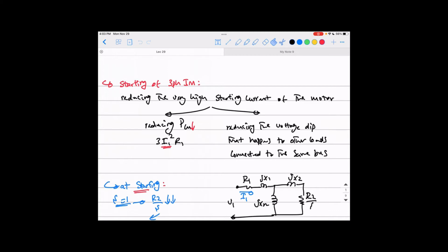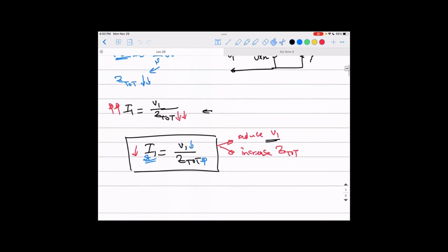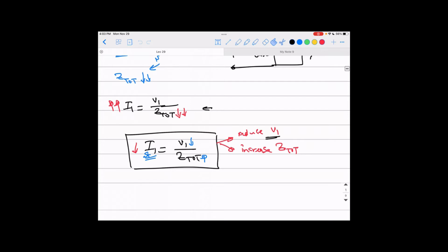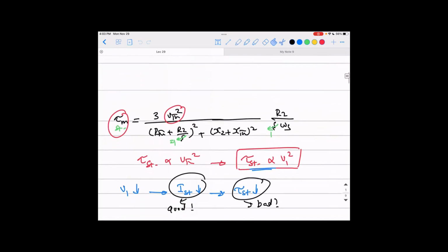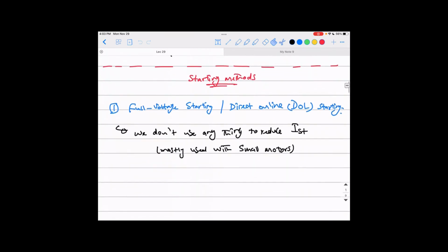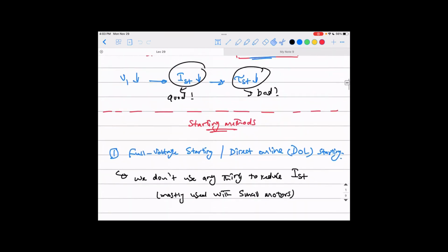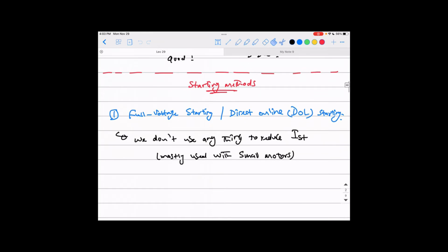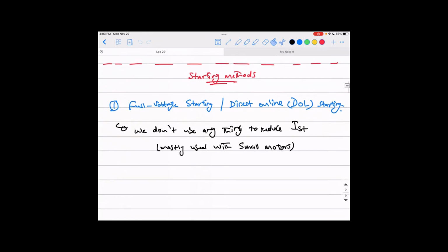Okay, so how to deal with this is basically, like we said, the starting current equals the voltage divided by the total impedance of the machine. The slip equals 1 at the starting instant. So basically, to reduce the starting current, you want to reduce the voltage of the machine or increase the total impedance of the system. Okay. So we just start talking about the methods we can go with to do this. Like we said, with the first one, the full voltage control starting, we call it direct online starting.